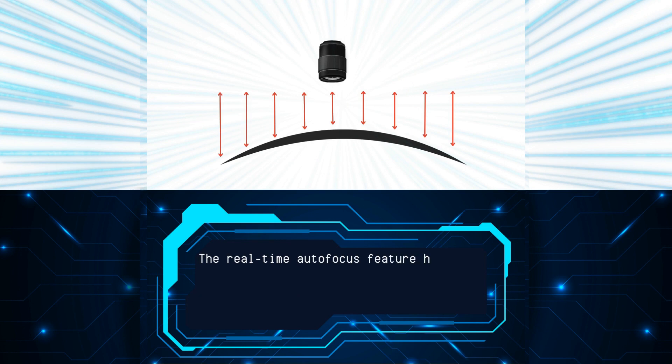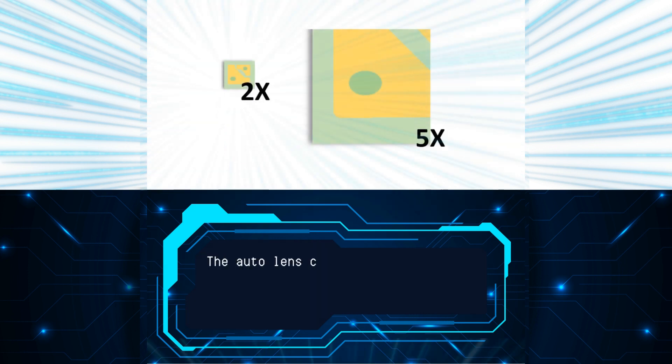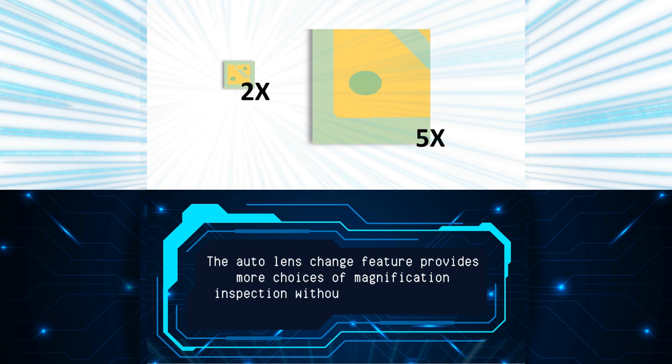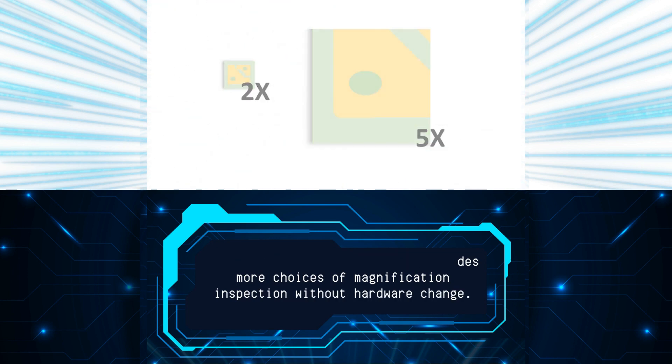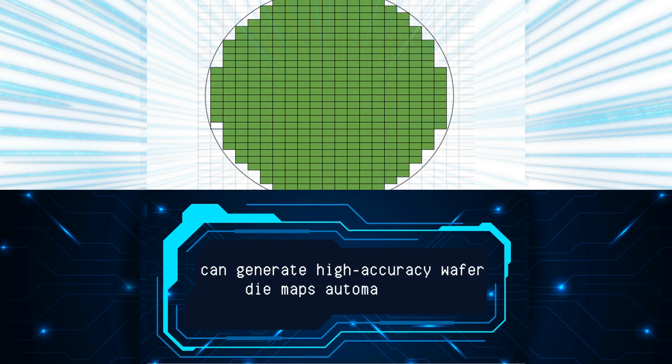The real-time autofocus feature helps solve wafer warp issues and enables consistent high-resolution image capture. The auto lens change feature provides more choices of magnification inspection without hardware change. Our wafer AOI can generate high-accuracy wafer die maps automatically.